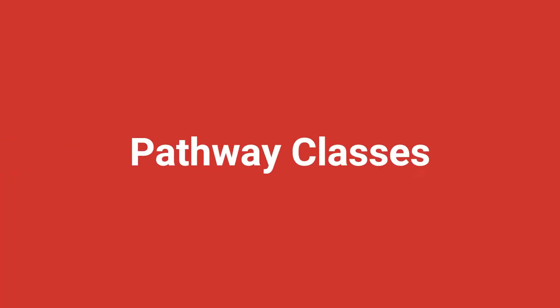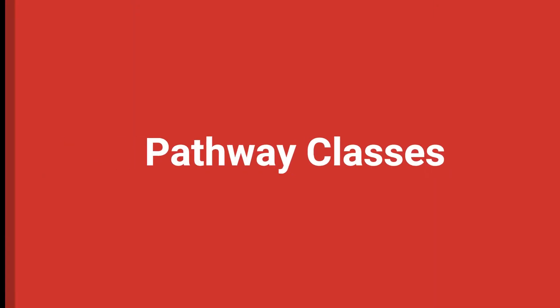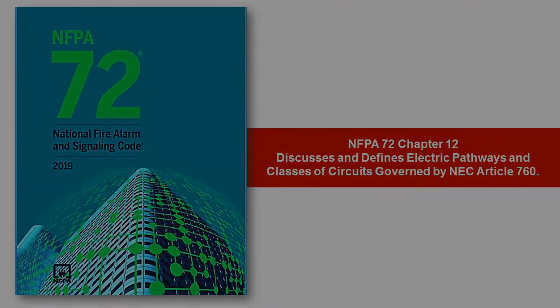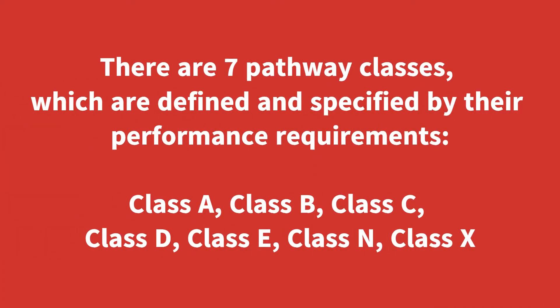NFPA 72 Chapter 12 discusses and defines electrical pathways and classes of circuits governed by NEC Article 760. There are seven pathway classes, which are defined and specified by their performance requirements. Class A is the most stringent pathway class and it has five critical must-have performance requirements.